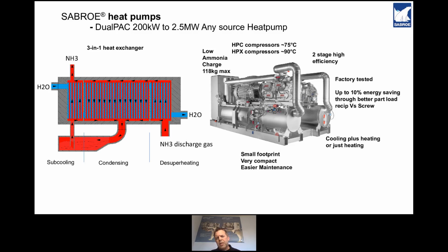Also, we use reciprocating compressors here. Now, we've looked at this, and in part load, reciprocating is better than a screw compressor version. So here we've calculated about 10% of your annual energy will be saved through using the part load of the reciprocating. But these things I can go into greater detail, but obviously I'm a bit pushed. We're only halfway up the Eiffel Tower. So next thing we have, like I said, small footprint, very compact and easy to maintain. It's a bit of a fallacy with the maintenance side of things, because basically these units can be maintained in situ, whereas eventually a screw would have to be removed from the unit, which is quite a big thing.